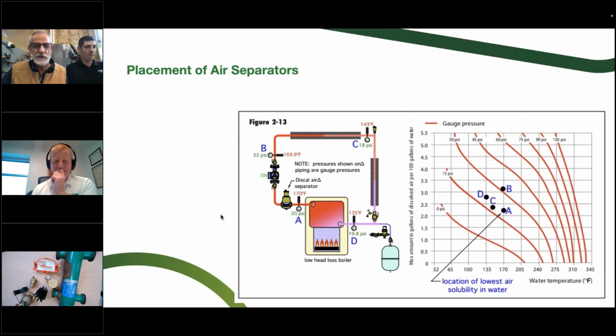And then in this picture, the two vents work together. So we've got the separator back at the boiler at the good spot, the hottest point. Then you notice the air vent on the top, where the end of the fin tube is. So that's position C. And if you look at the graph over there, that's the second best place to get it out because that's the lowest pressure. And that's also the point where in the off season, any air that you didn't get out is going to migrate up to that high point. And that's what that float type of air vent can handle in conjunction with the separator.